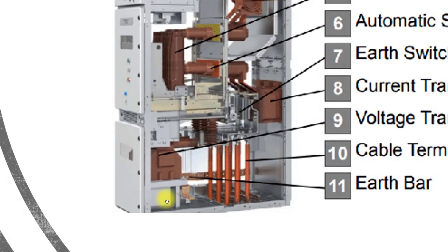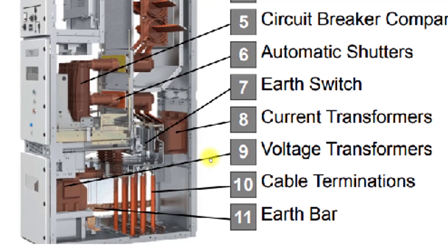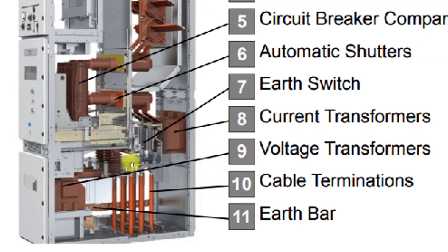Number nine is the voltage transformer. This VT has only one primary connection visible — the other connection is to ground — and you can easily recognize it as a VT. Cable compartment access is from the bottom. The VT can be racked out; the connections are arranged to allow this, and the primary fuses are also placed within this racking connection.